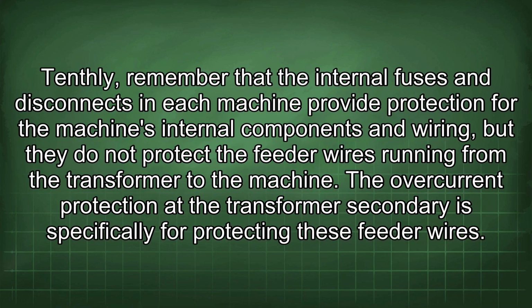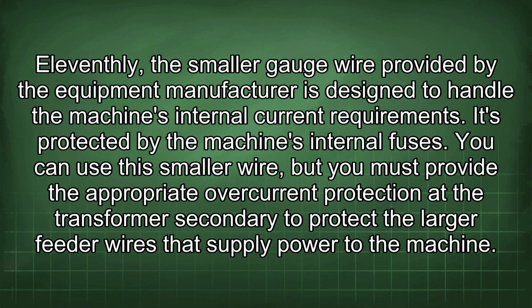Tenthly, remember that the internal fuses and disconnects in each machine provide protection for the machine's internal components and wiring, but they do not protect the feeder wires running from the transformer to the machine. The overcurrent protection at the transformer secondary is specifically for protecting these feeder wires. Eleventhly, the smaller gauge wire provided by the equipment manufacturer is designed to handle the machine's internal current requirements. It's protected by the machine's internal fuses. You can use the smaller wire, but you must provide the appropriate overcurrent protection at the transformer secondary to protect the larger feeder wires that supply power to the machine.